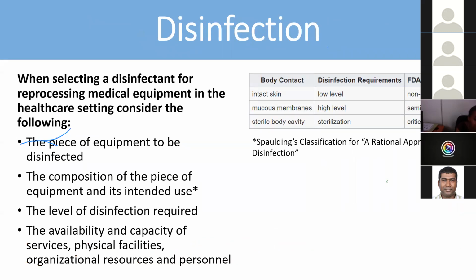Okay, disinfection. When you select a disinfectant for reprocessing medical equipment in a care setting, consider the following: the piece of equipment to be disinfected, its composition and intended use, the level of disinfection required, then the availability and capacity of the service, physical facility, organization resources, and personnel. So when you talk about body contact: intact skin needs low-level disinfection, FDA device class non-critical. Mucous membranes need high level, semi-critical. And sterile body cavities need sterilization, critical according to the FDA device class.